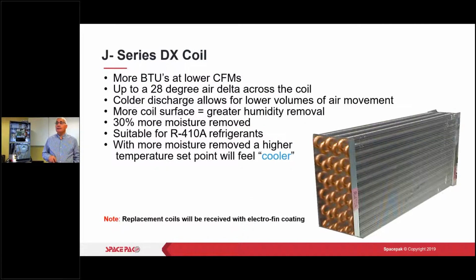So we're still doing that DX coil. It's still a 6-row coil. And because of that, this is how we get that 30% more moisture removal from our system. So again, the claim to fame with SpacePak is, especially in cooling, 75 will feel more like 72. So 77 will feel more like 74, 75. Right? So they can have an actually higher set point, but it'll be much drier in their home.